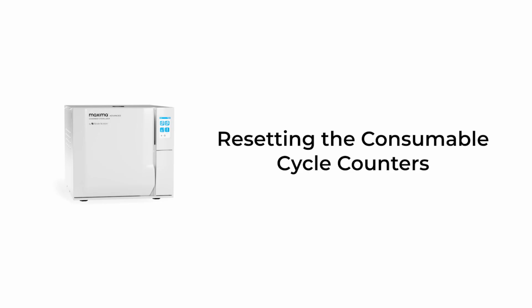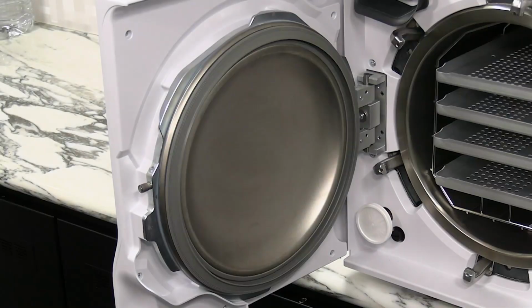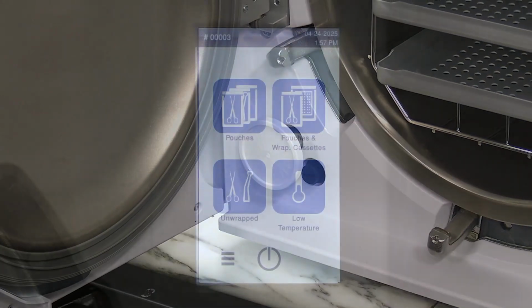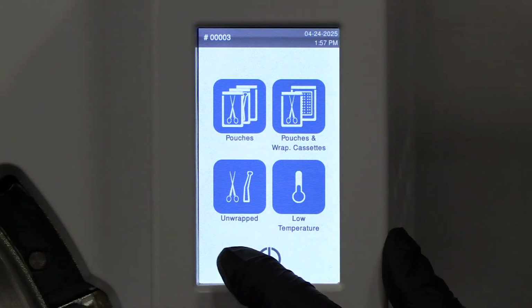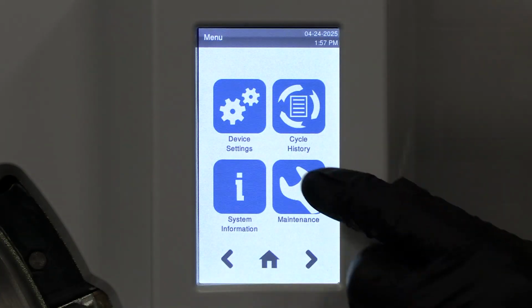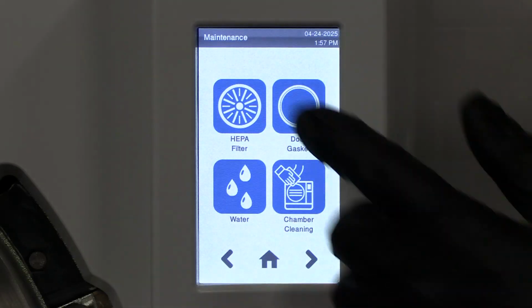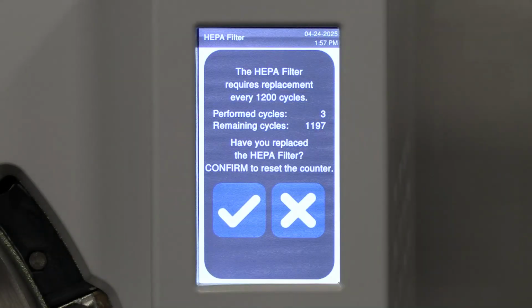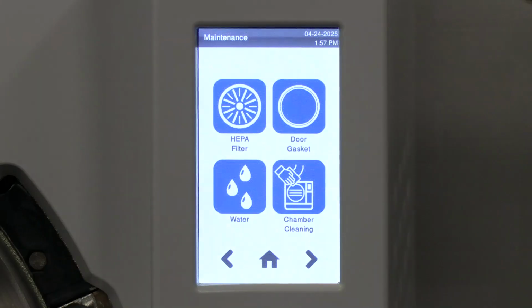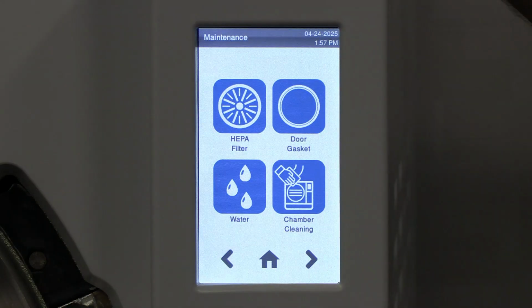Resetting the consumable cycle counters. After replacing the door gasket and/or the HEPA filter, you will need to reset their respective cycle counters. Using the hamburger menu on the touchscreen, tap the maintenance icon and then select the consumable you have replaced. A message will display the number of cycles currently performed and how many cycles remain before needing to replace the consumable. Tap the confirm button, the checkmark icon, to reset the cycle counter for the replaced consumable.